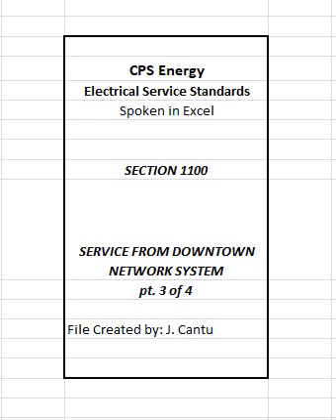8. The opening and sealing of penetrations into transformer vaults or rooms for customers' conductors shall be closely coordinated with the CPS Energy customer service representative. This work shall be done by customer and must be watertight and not permit rodent penetration. All sealant used inside the transformer vault or room shall be approved and sealed per NFPA codes with the appropriate fire rating.